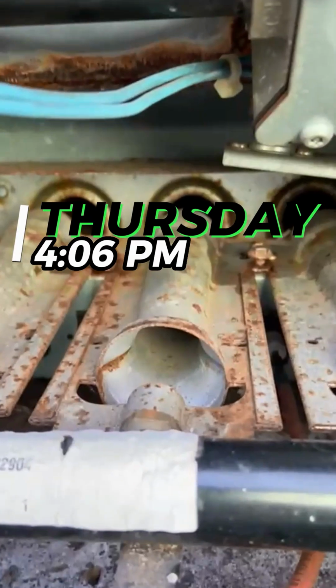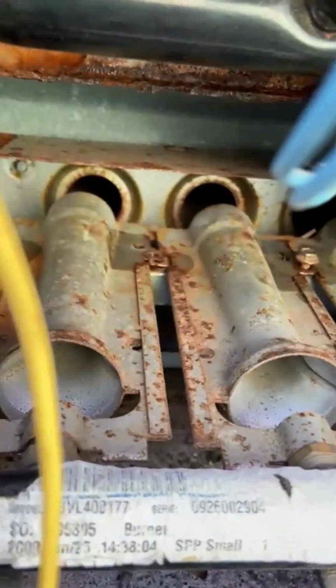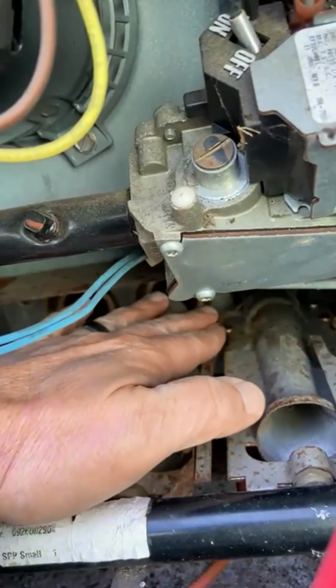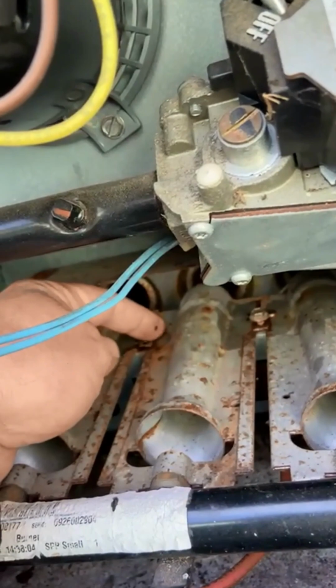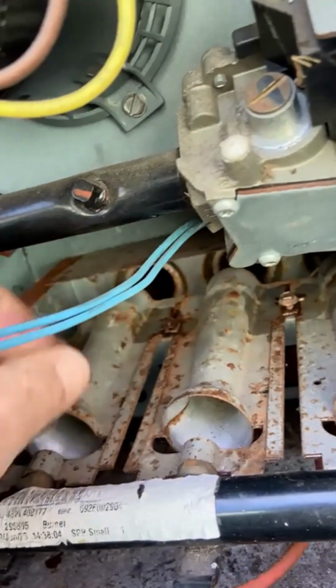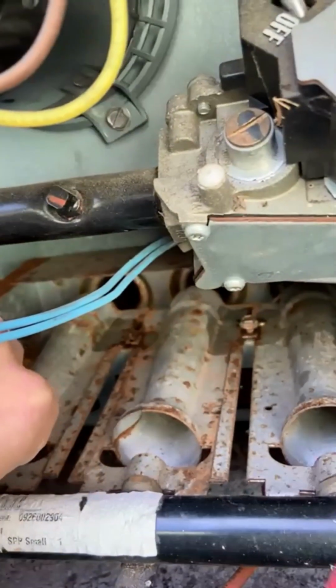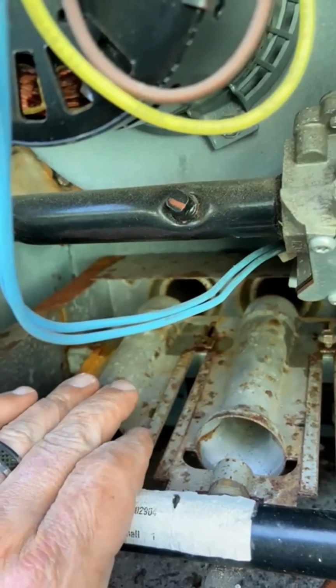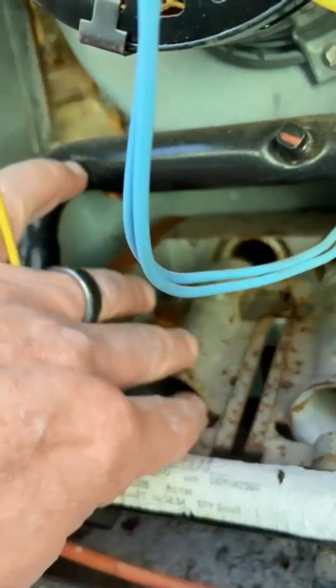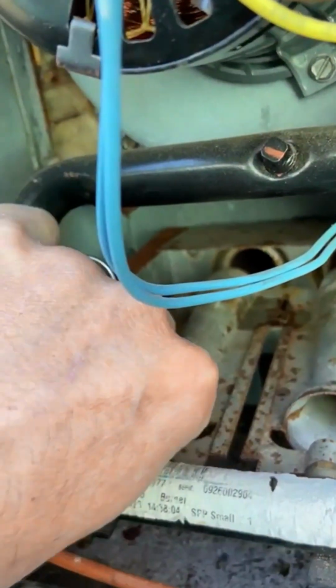So I'm over here at another customer's house. This is an old Carrier, and it's real hard to get these screws out to get them out to clean. But this burner was dead. The flame sensor's under it, so you got to take it out to get to the flame sensor.